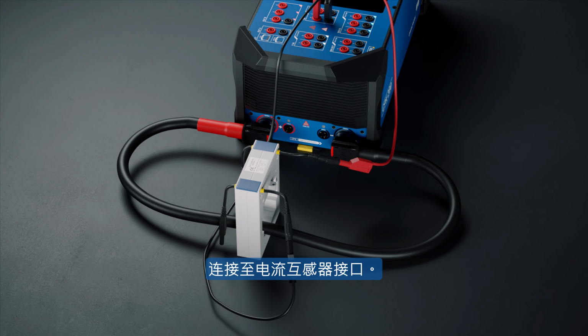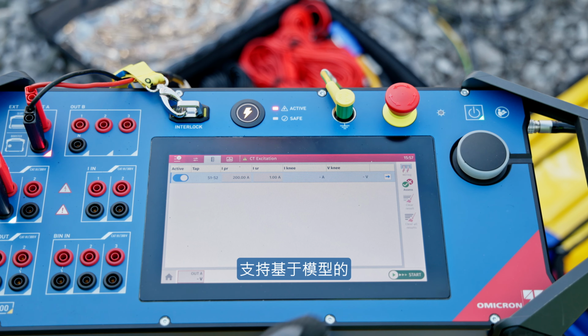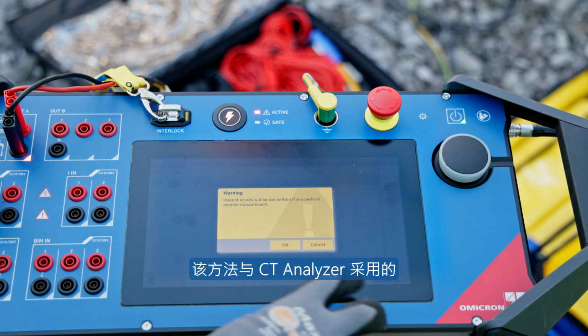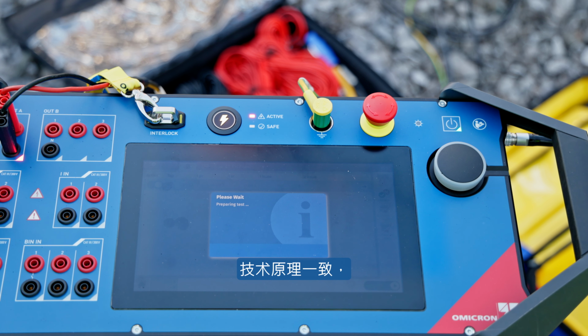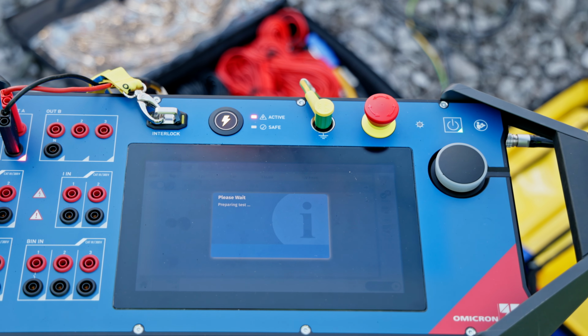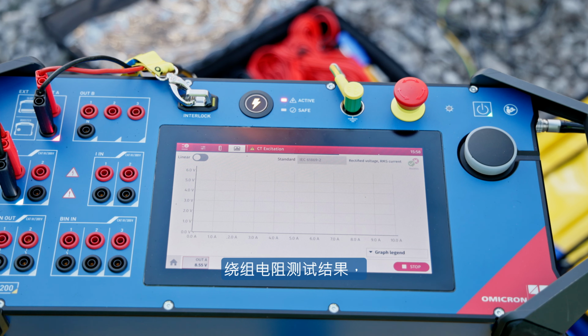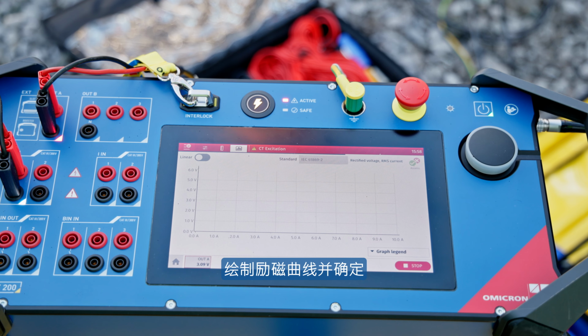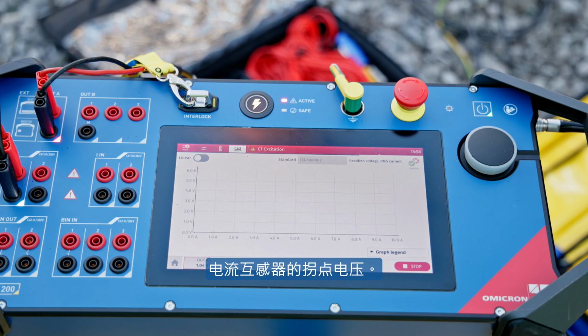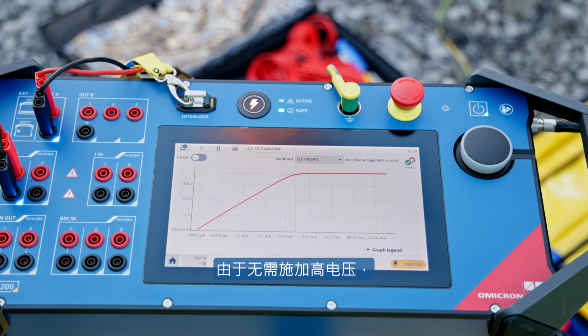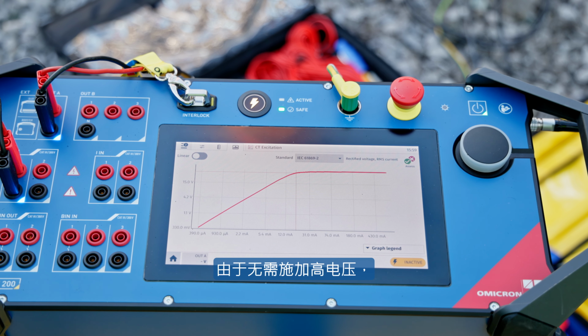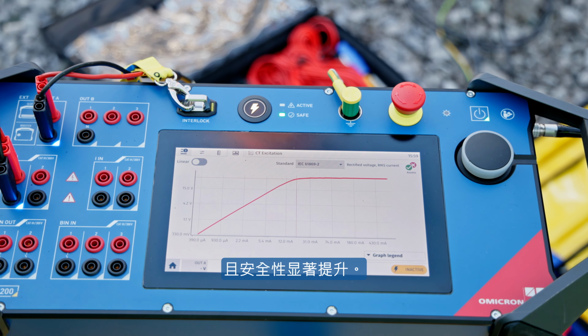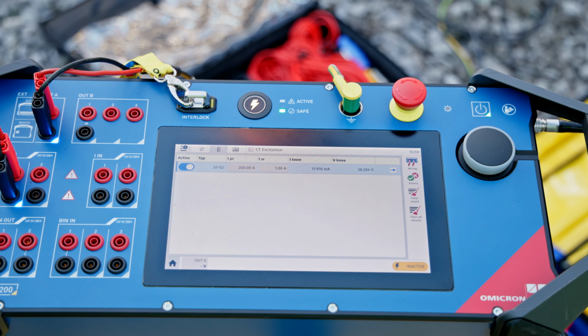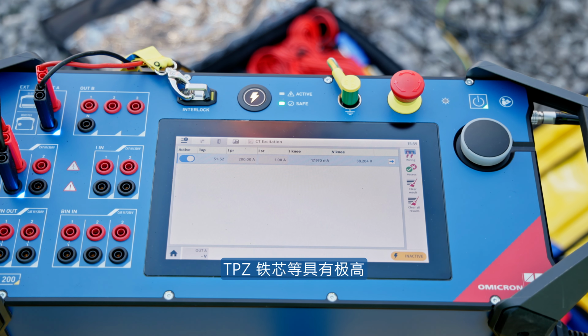The CPX200 now also offers CT excitation curve measurements with the model-based approach users already know from the CT Analyzer. This approach is well established in standards by now and uses the results of the ratio and winding resistance tests to plot the excitation curve and determine the knee point voltage of the CT. This allows more precise, faster, and much safer testing due to no high voltage being necessary. With this approach, we can even test CTs with a very high knee point voltage, like TPZ cores.